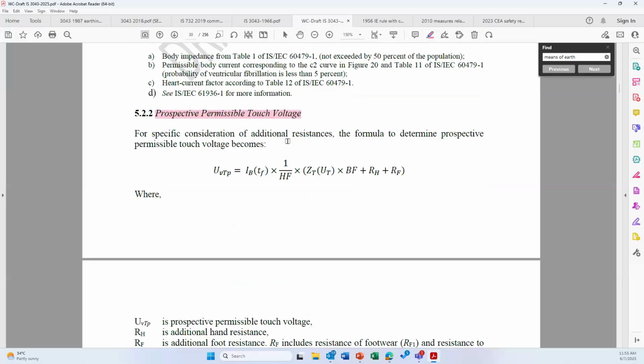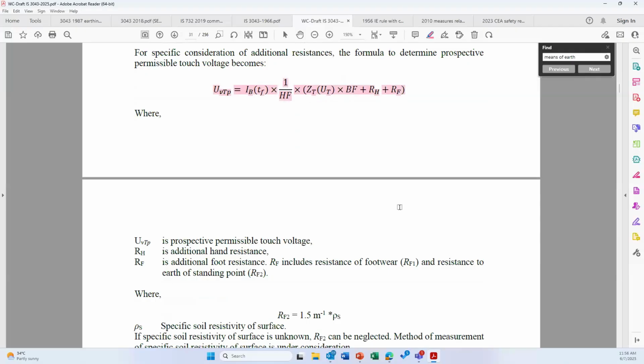imagine an electrical installation where the touch voltage is 115 volt for 1 second, and you are not able to reduce the touch voltage lesser than 115 volt. Under that condition, one of the methods which can be adopted is you allow only skilled people to be allowed in this particular substation, and the people always should have PPEs like shoes, like gloves, and so on. Now the prospective permissible touch voltage based on the additional resistances offered by the gloves, offered by the shoes, offered by the resistance of the gravel can be calculated based on this.